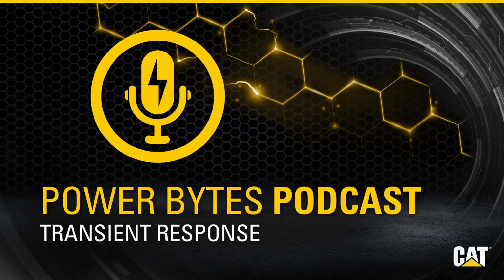That's fantastic. Bryan, this has been some really great information. Are there any last recommendations you can provide for users that are evaluating their transient responses? Yeah, there are some general items that we would normally look at and recommend for applications with a particular focus on transient response capability. So first thing, we would look at an externally sourced excitation system.